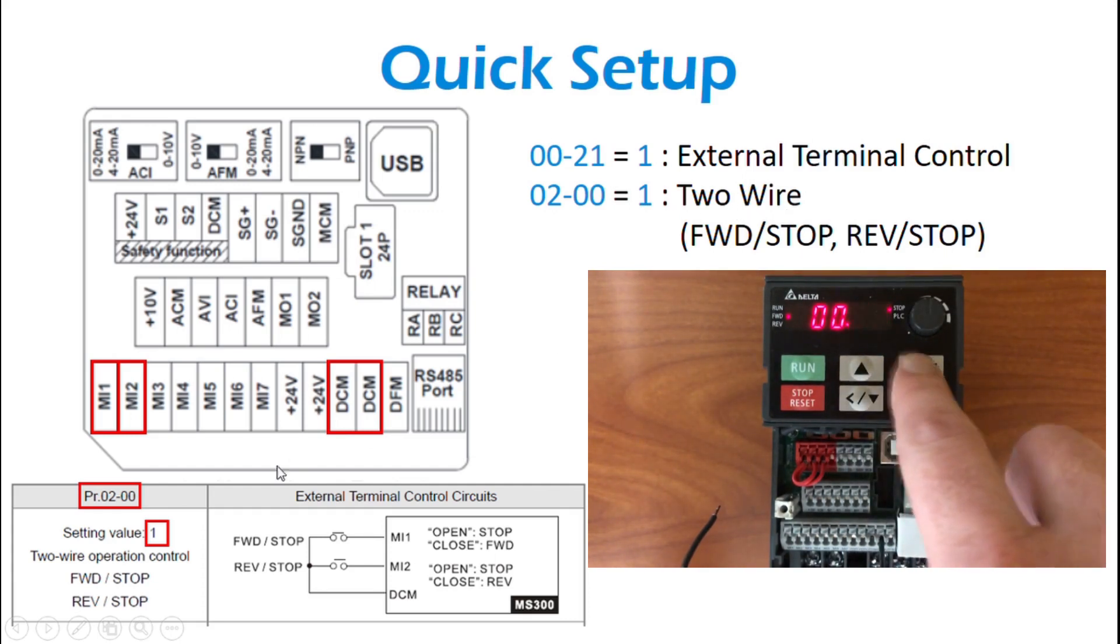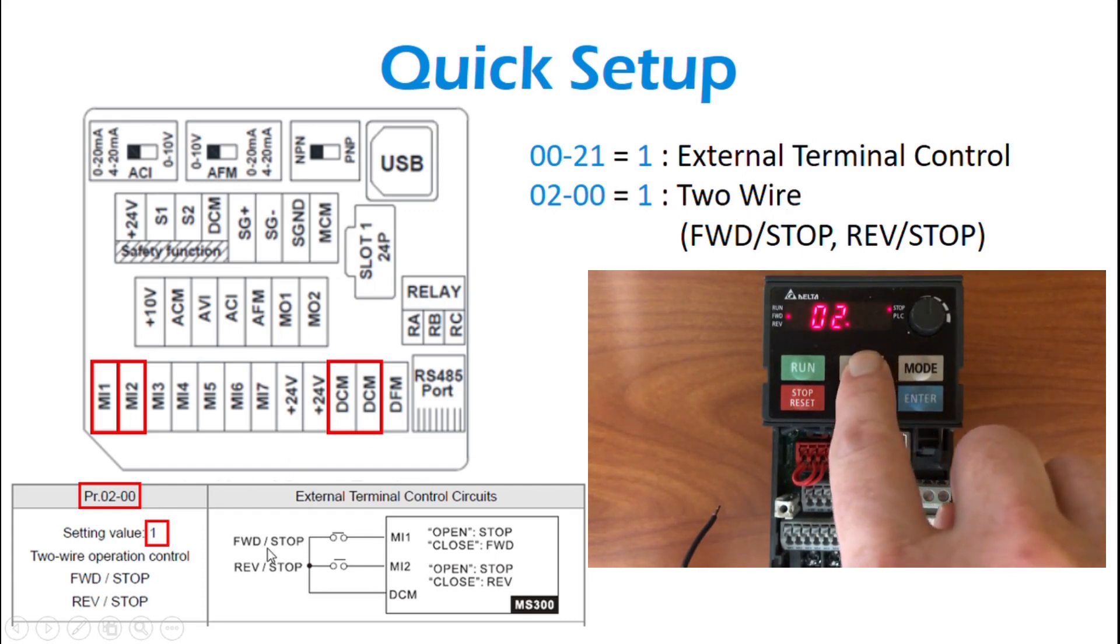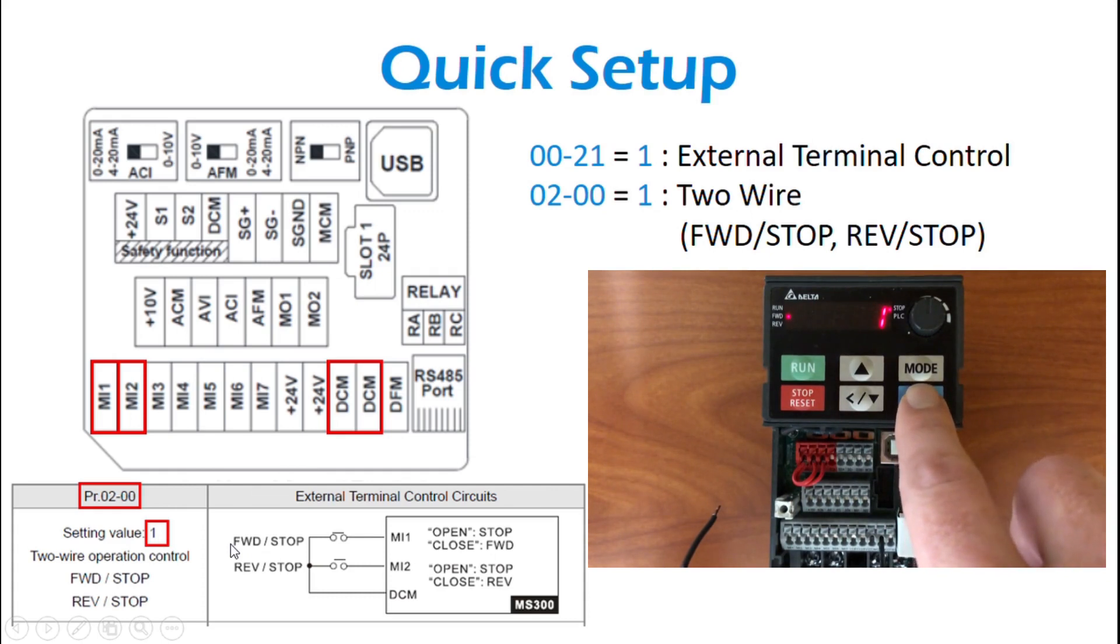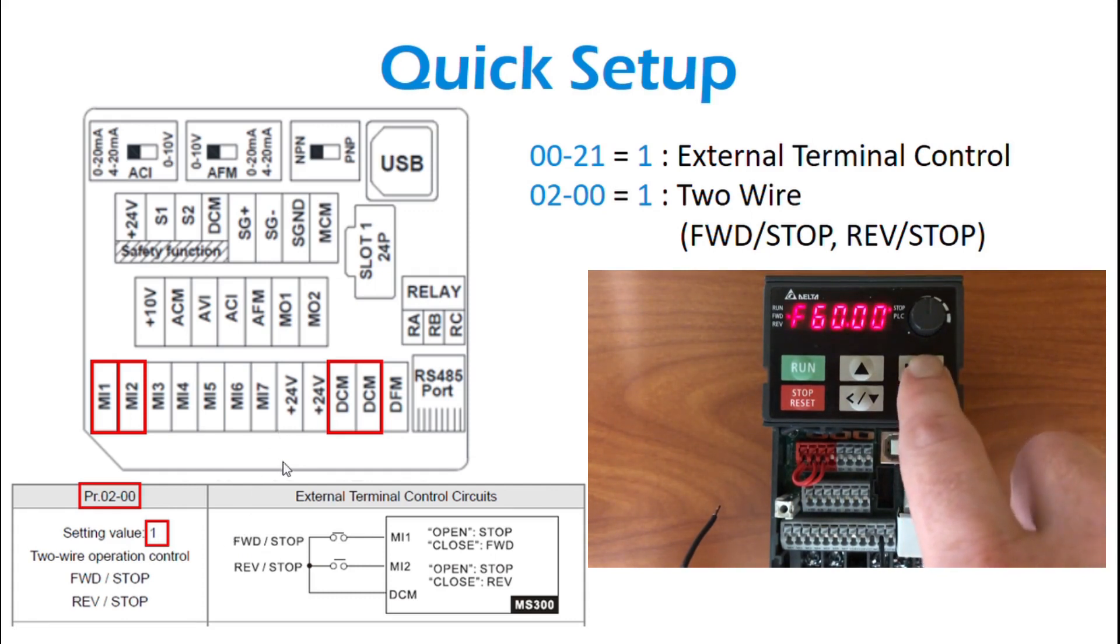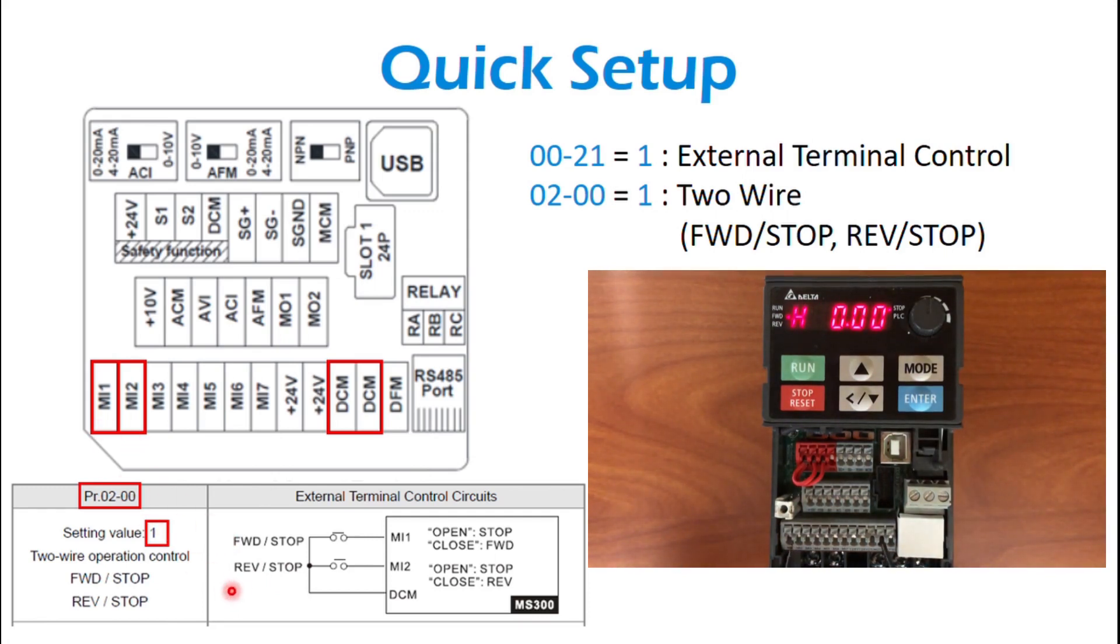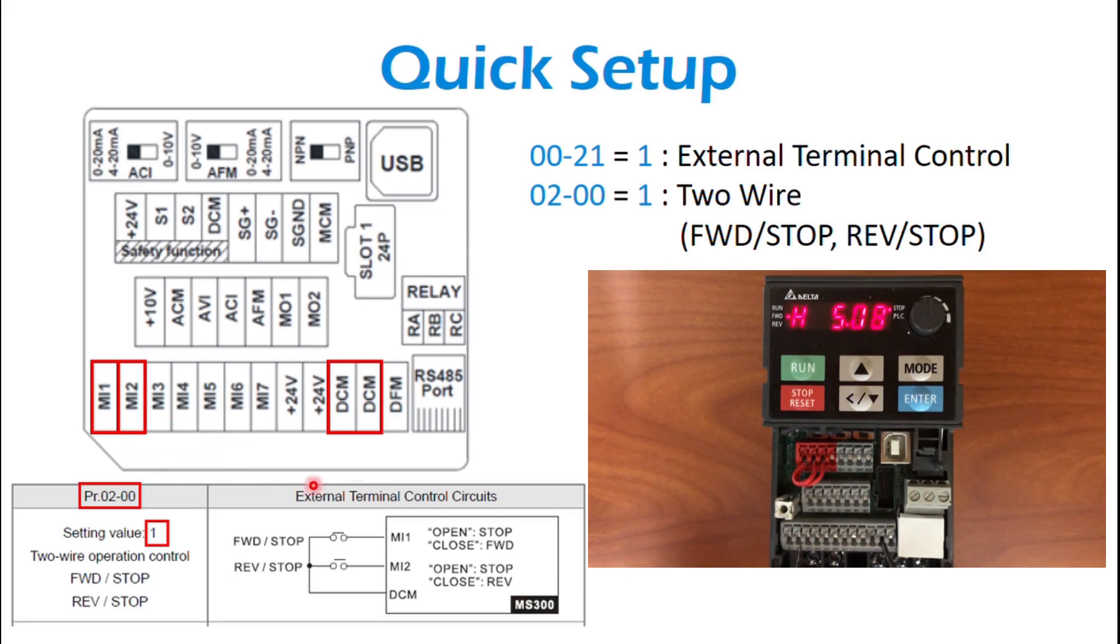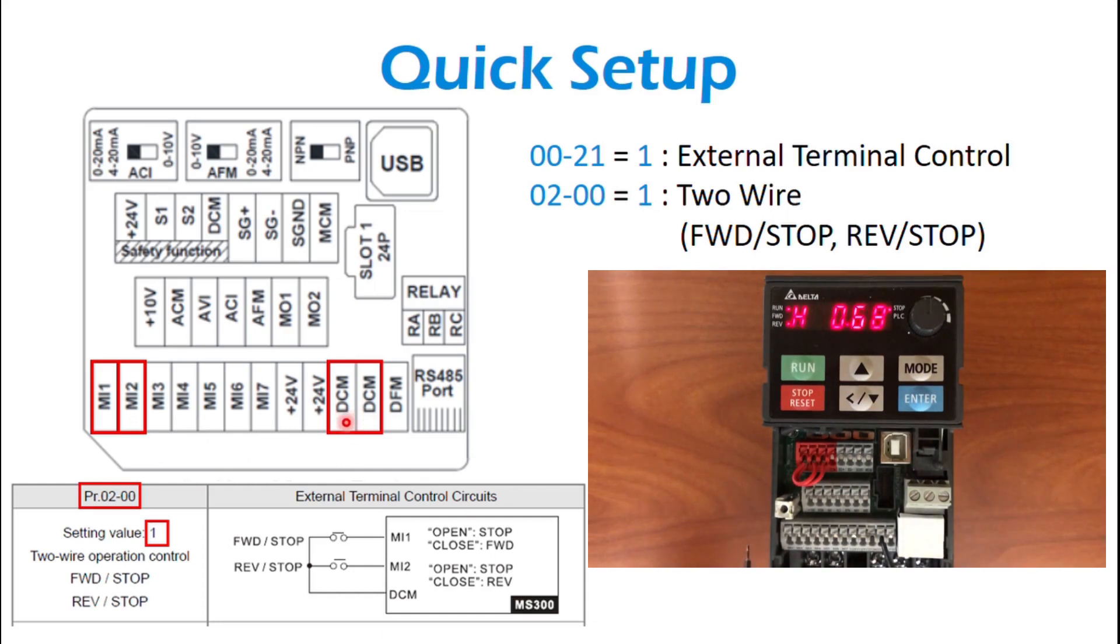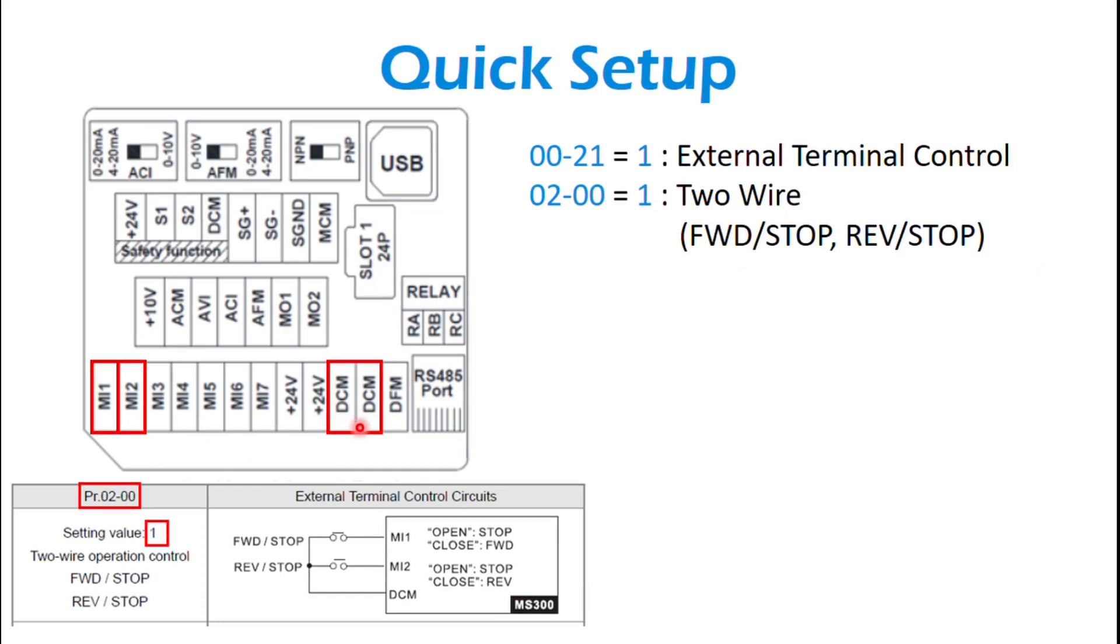This setup, you've got forward stop to MI1, reverse stop to MI2, and it's just a dry contact to your DCM terminal. Both DCMs are tied together, so either one of those points is fine. And that's pretty much it for a two-wire setup.